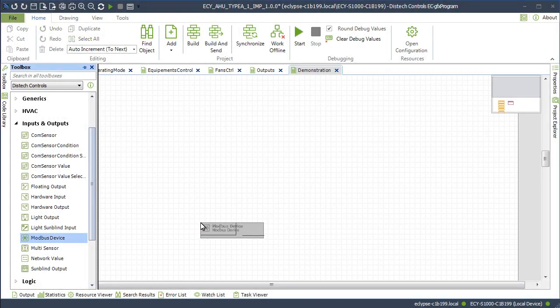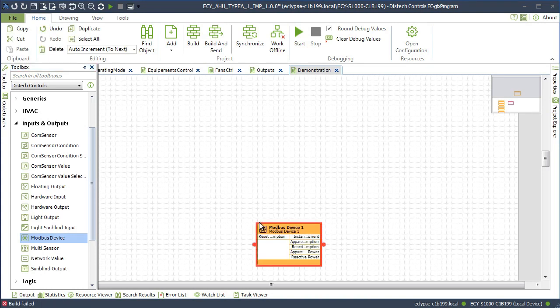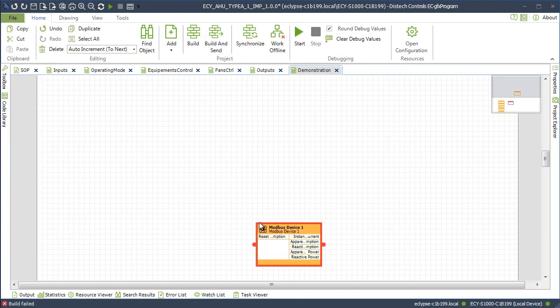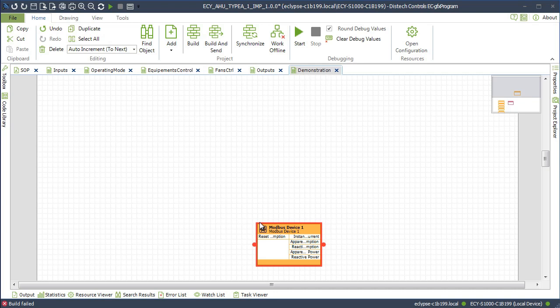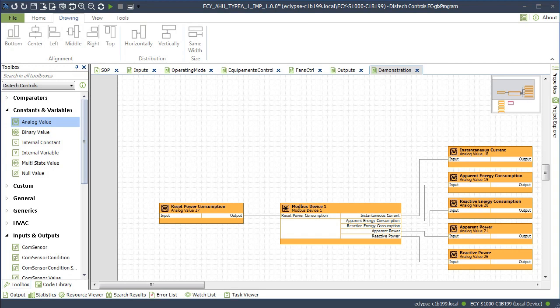The connected system controller now supports Modbus RTU through its RS-485 port and Modbus TCP IP through the IP network. The Modbus device values are brought into an ECGFX programming sheet using the new Modbus device block. Modbus device block inputs and outputs can be linked to BACnet objects, thereby making them available for use in Envision graphics.